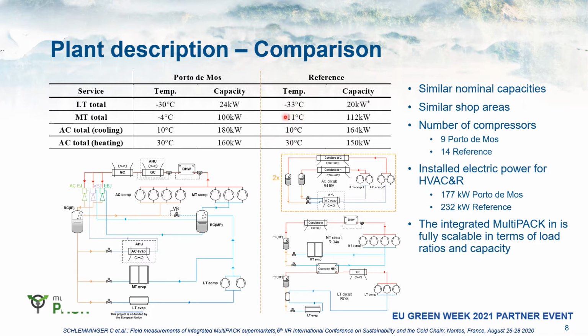For example, the nominal evaporation temperature on the MT level is much lower for the reference side than for the MultiPACK side. If we count the number of compressors, we see that the Porto de Mos MultiPACK side has a substantially lower amount of compressors installed, whereas the reference has 14 compressors. The installed electric power is 177 for Porto de Mos, while about 230 for the reference side.